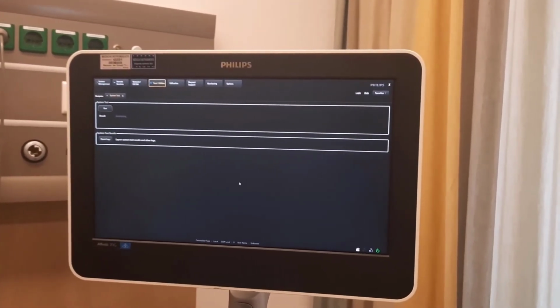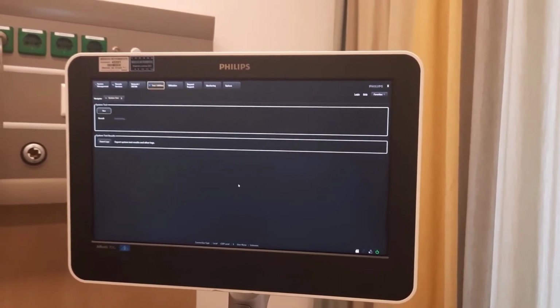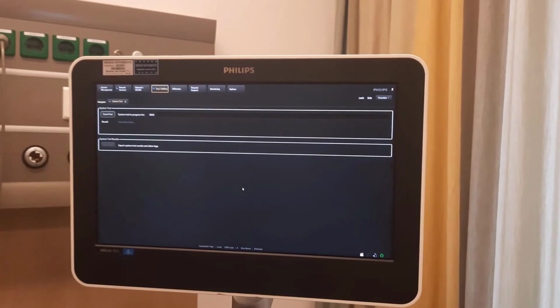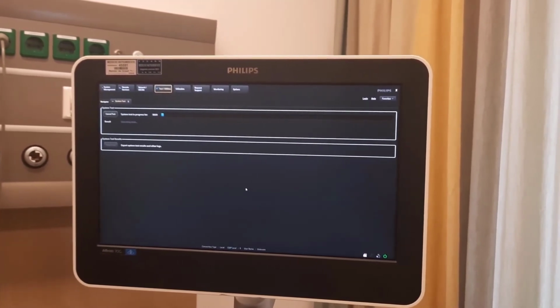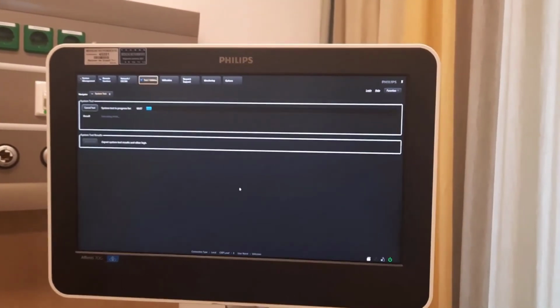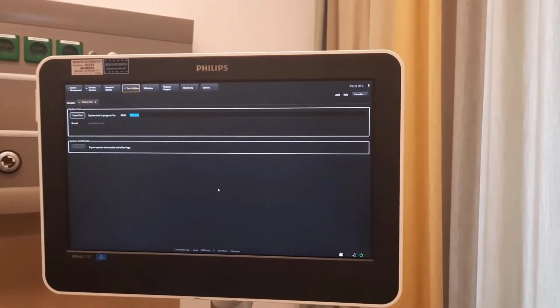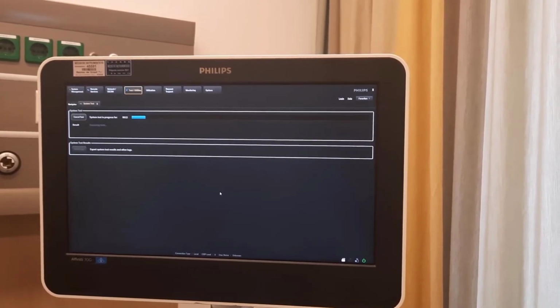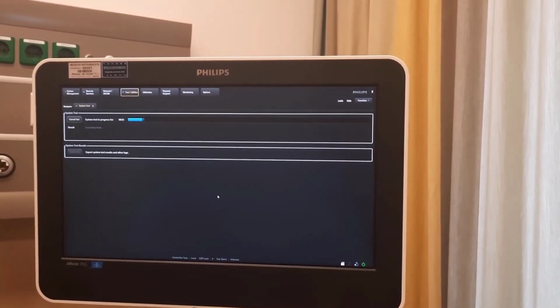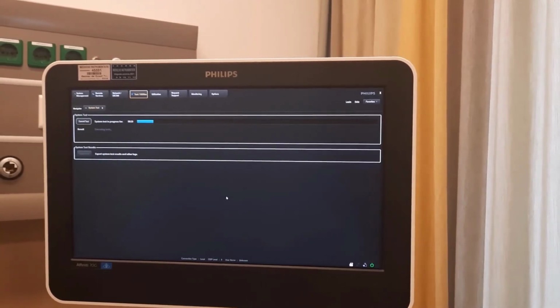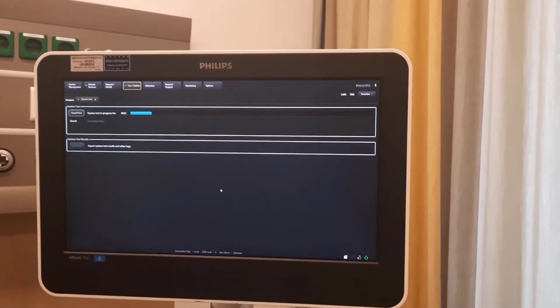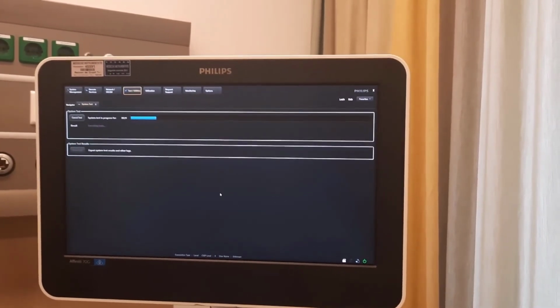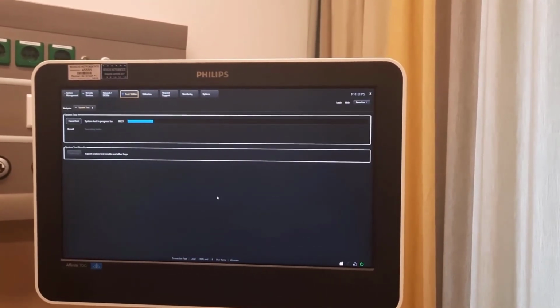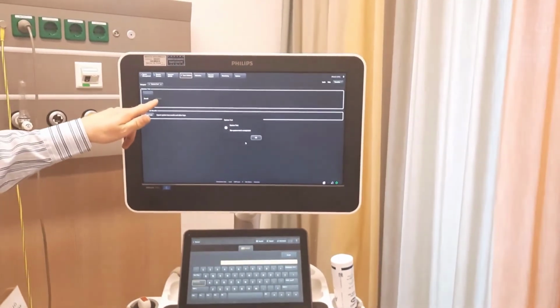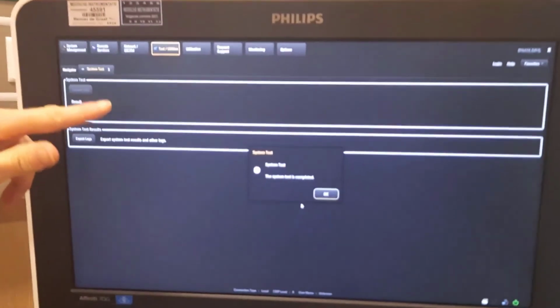Now it checks all the internal parts of the transducer. Afterwards you can export the log file and send it to Philips if there is any problem with the machine. We do this test yearly when we do preventive maintenance, just to make sure that everything is okay when we return the machine to the department. Test is completed and it is passed. When it has failed, then it's in red. It gets a message failed.